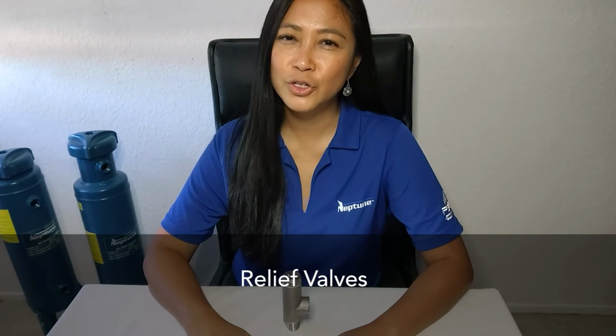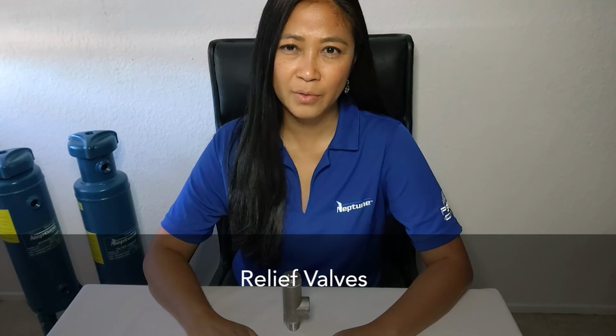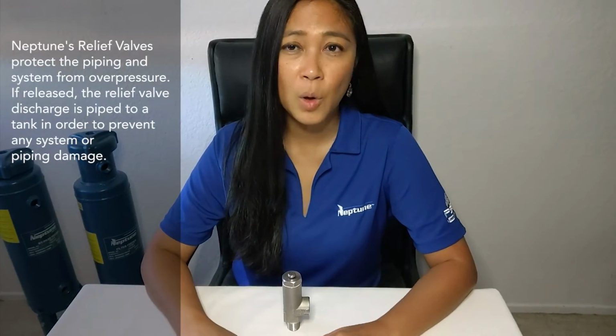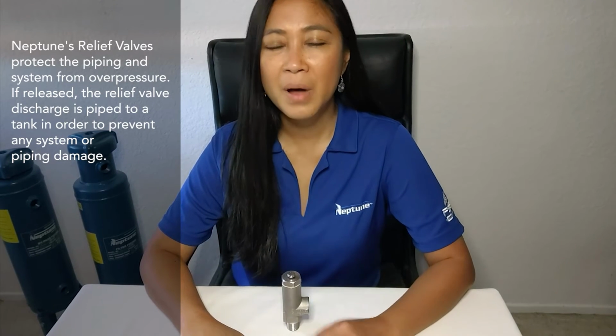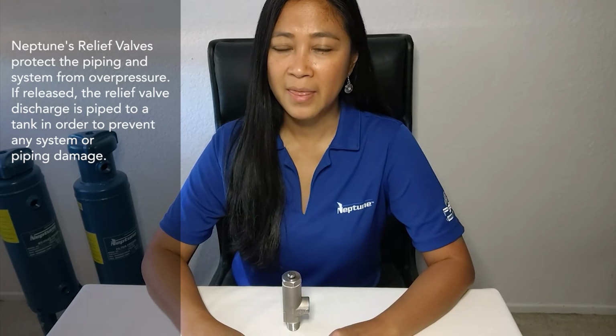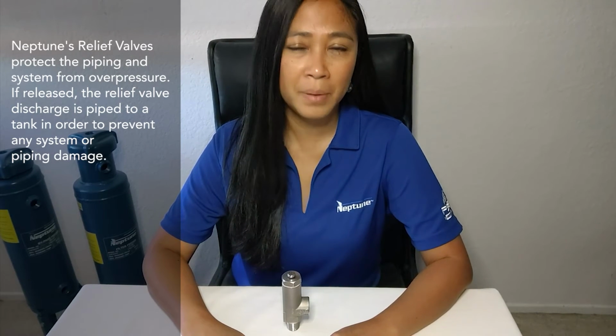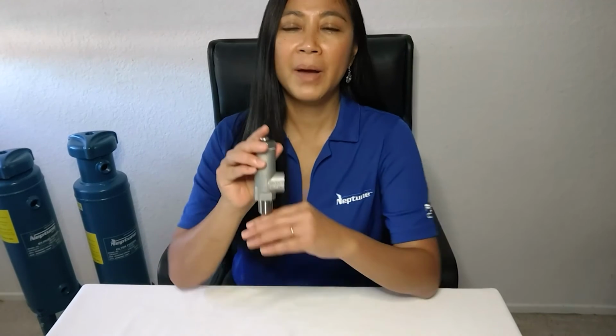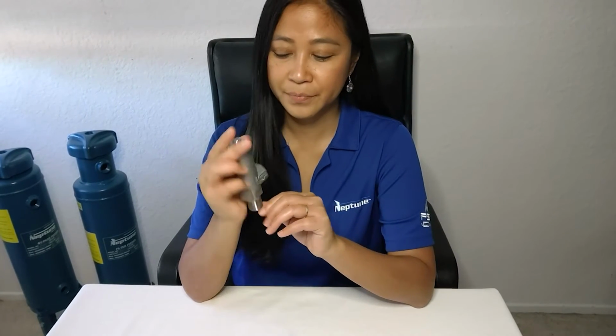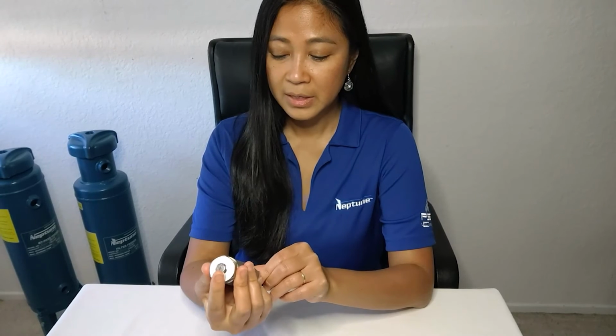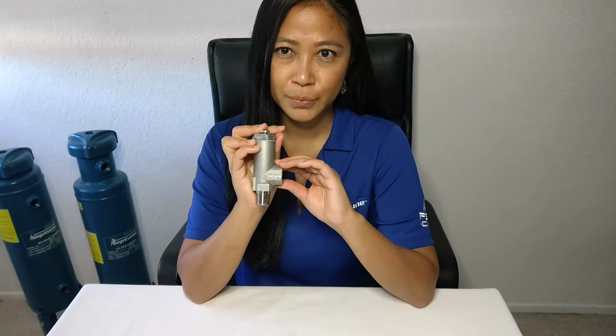Another accessory that I like to share is the relief valve. The relief valve maintains a set pressure at the discharge line or discharge port to protect from being over pressurized. Some pumps come with an internal relief valve, and that internal relief valve is to protect the pump. Most applications recommend an external relief valve to protect the piping, the system, or the application from being over pressurized. The relief valve is set at 50 psi or 10% above the maximum operating pressure.